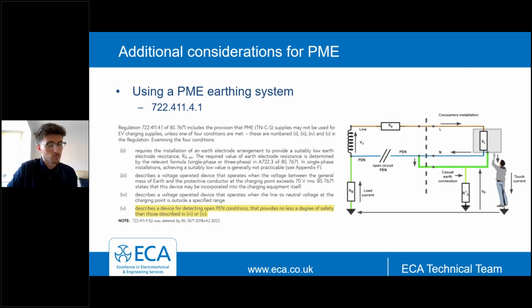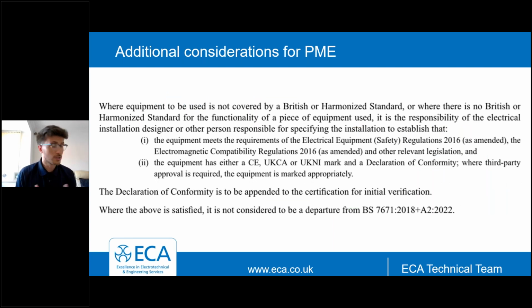Following on from this regulation on page 326, there is a note, and then further information is provided within this clause of the regulation. It discusses where equipment is not covered by British or harmonised standards. The device just referred to in indent 5 of regulation 722.411.4.1, relating to the open PEN device, is not currently covered by a British or harmonised standard. So when selecting a piece of equipment that isn't covered by a British or harmonised standard, it is the responsibility of the installation designer or other person responsible for specifying the installation to establish that this equipment is suitable to provide the relevant protection and to fulfill the requirements of this regulation.